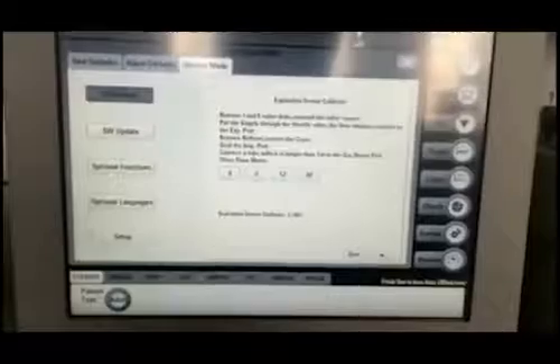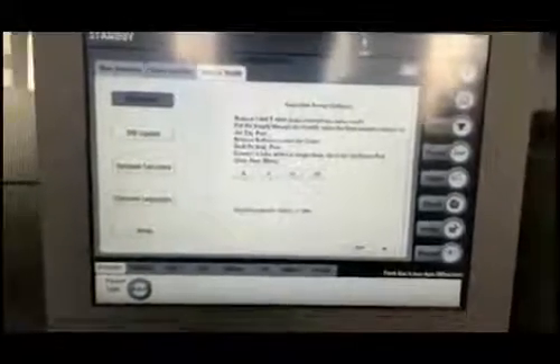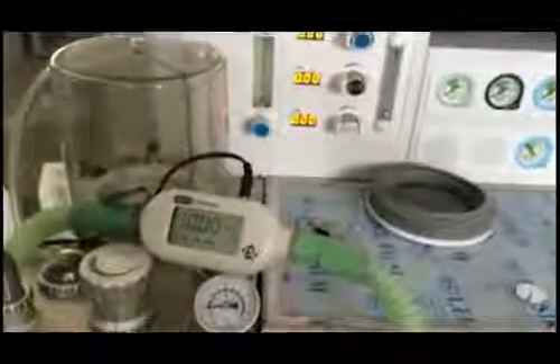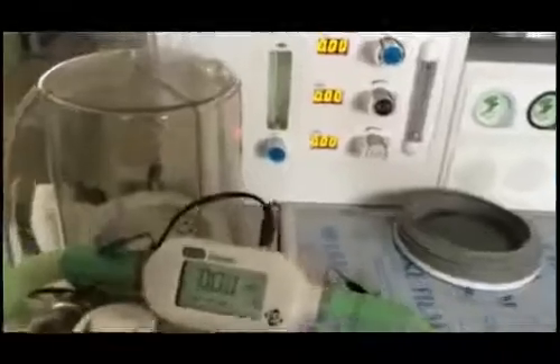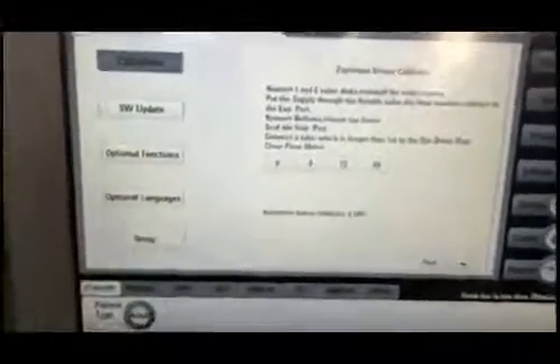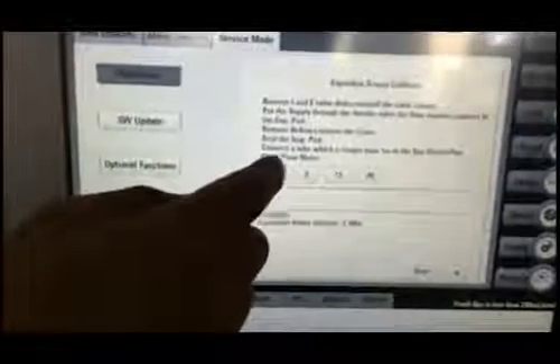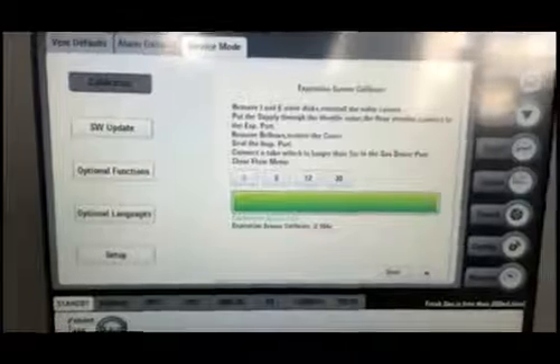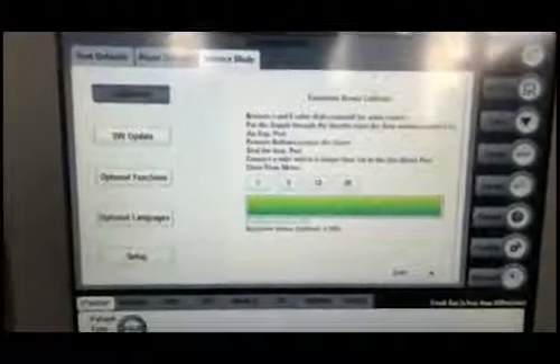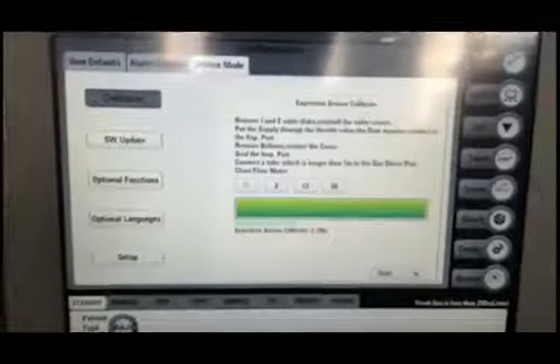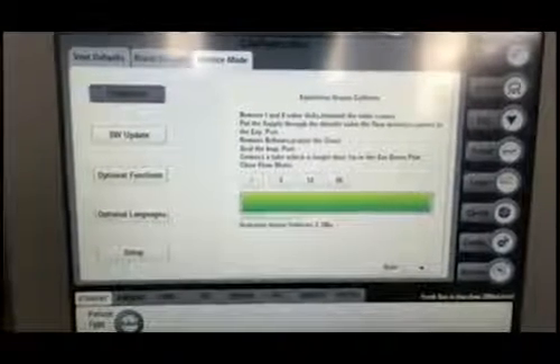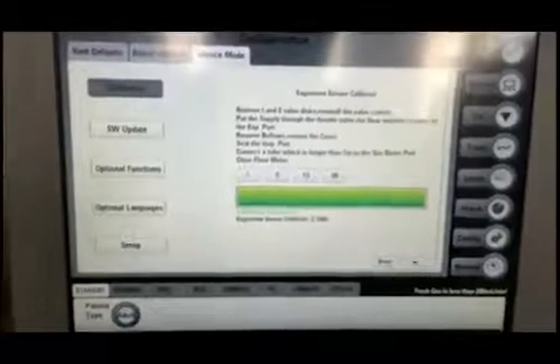Before pressing the 0, 3, 12 or 30 button on the screen, please look at the flow meter. As you can see, the flow meter displays 0. The first step of the calibration is that before you touch this button on the screen, you have to make the flow meter go to 0. As the flow meter is 0, now you can press this key. After the calibration is complete, the calibration successful sign will be displayed. The calibrations must be performed in order 0, 3, 12 and 30. All the units are in liter per minute. The units displayed on the flow meter are also in liter per minute.